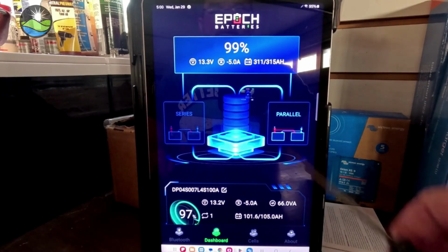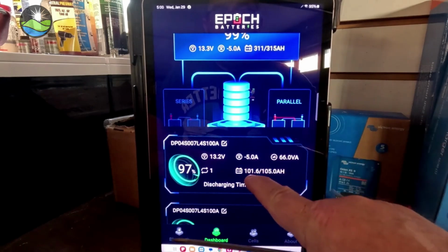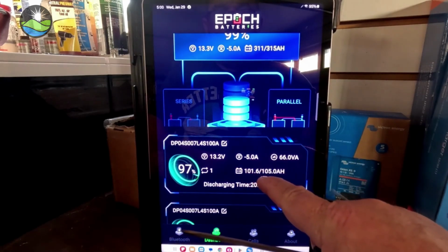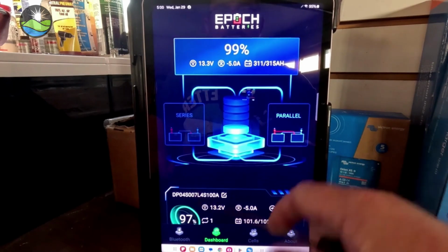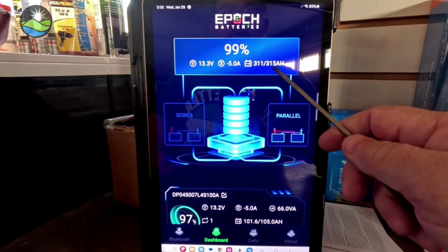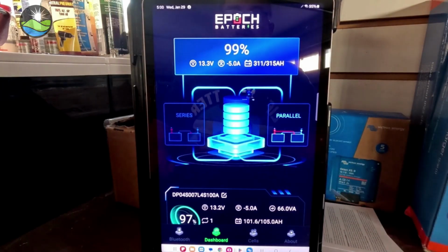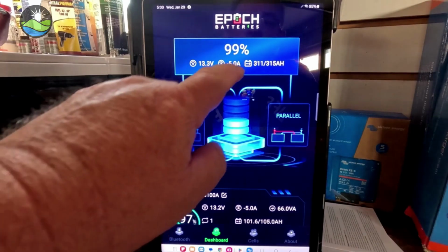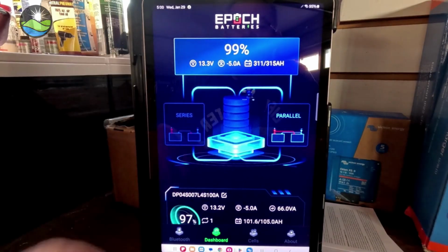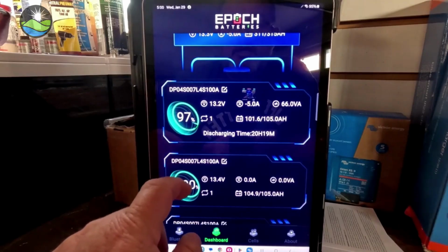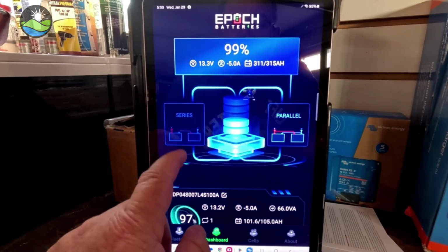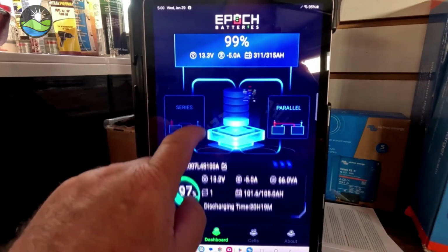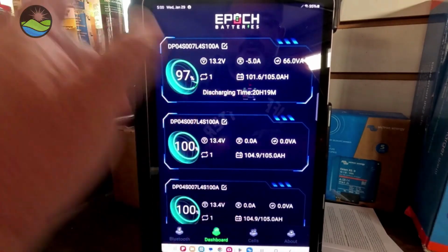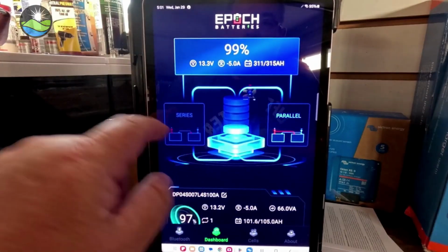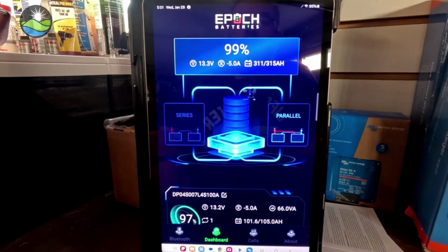So this totalizes everything. As you know, we have 101.6 amp hours remaining of 105 amp hours, but up here we have 311 of 315 available. So it's totalizing all 3 batteries. And it's still only showing that we're pulling 5 amps because we're only pulling it from one battery. Now if these batteries were electrically connected, it would still pull 5 amps, but it would distribute this over the 3 batteries. Each one would pull like 1.5 amps or 1.3 amps, something like that. So that's how that works.